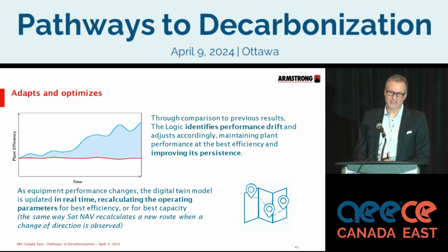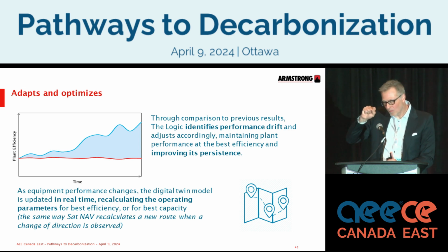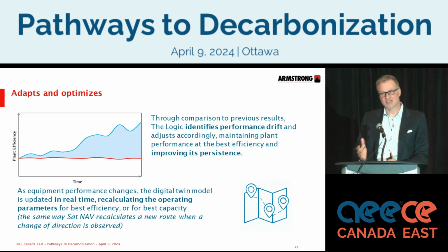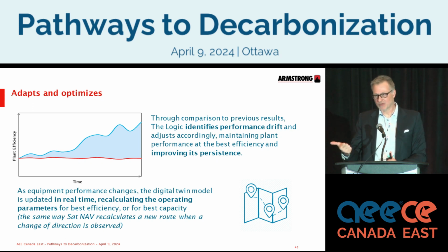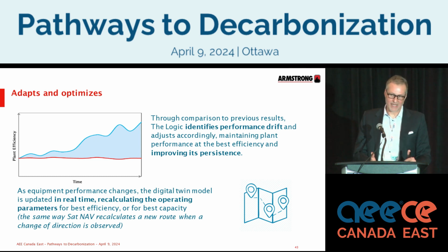Through the diagnostics, we actually determined that an MRI loop in the system, when that MRI machine was up and running and it was drawing cooling, created that increased pressure requirement in the system. End result, we put a pony pump in that loop, and the overall head on the primary loop dropped by 20%. So that's where, walking through here, optimization is strictly demand-based controls with performance maps that factor in efficiency.